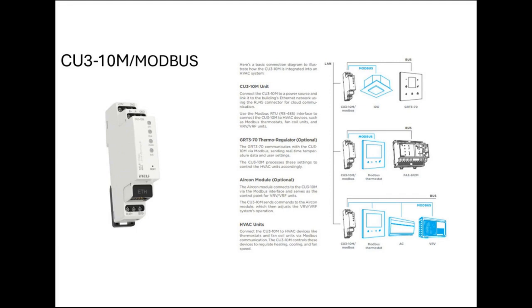Then in case two, you can use any Modbus thermostat. If it is an existing one, you can use that existing Modbus thermostat and connect it to the CU310 Modbus terminal and switch on or switch off our fan coil unit, or use our actuator to turn the heating or cooling outputs on or off. Then you can use it to control and turn this HVAC system on or off completely. We will get information from the Modbus thermostat registers, and the CU310 will act as a master and get this information from the Modbus. We can read these parameters from the thermostat, and it will act. It will turn the fan speed of the FCU on and off in the Modbus line.